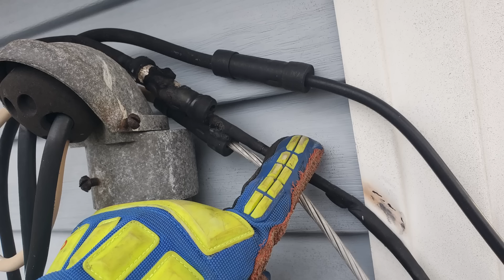Also, on the siding, the wire was chafing against it enough that it wore completely through the insulation, so the live wire was making contact with that siding. I'm not sure how those wires got up in behind that weatherhead. I can assume years ago someone working on the siding must have tucked them up in behind there. I hope it's not something a lineman would ever do, but this could have been bad if it had made contact with that mast or weatherhead. It likely would have arced for quite a while, and probably would have burnt the wires completely off before ever opening the cutout on the transformer.